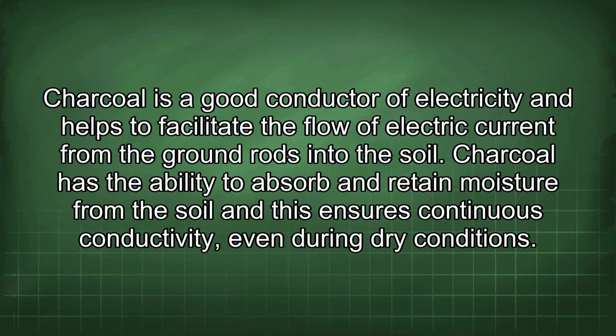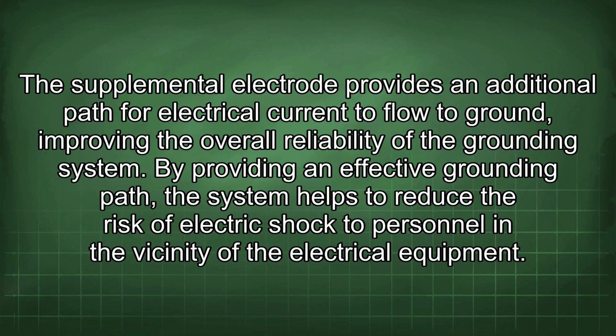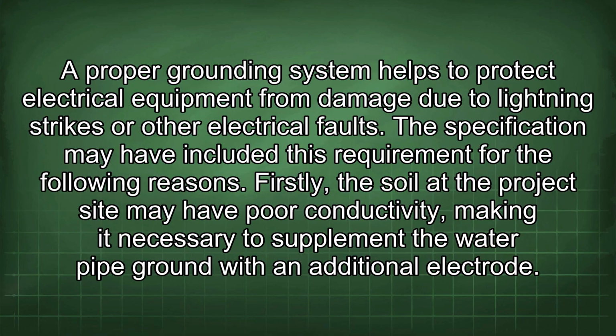Charcoal has the ability to absorb and retain moisture from the soil, and this ensures continuous conductivity even during dry conditions. The supplemental electrode provides an additional path for electrical current to flow to ground, improving the overall reliability of the grounding system. By providing an effective grounding path, the system helps to reduce the risk of electric shock to personnel in the vicinity of the electrical equipment. A proper grounding system helps to protect electrical equipment from damage due to lightning strikes or other electrical faults.